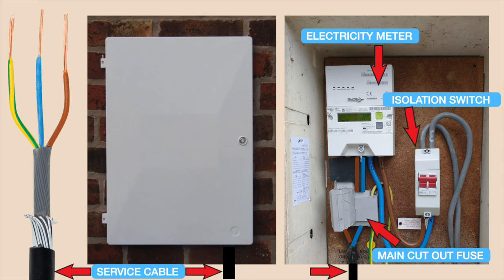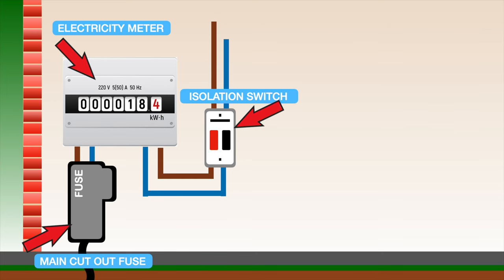On the left-hand side of the screen that's generally what a service cable will look like, and then the left picture shows what a meter box looks like from the outside and the right picture shows what a meter box looks like when it's opened up. The electricity comes in through the service cable at the bottom. It then goes through the main cutout fuse, which is usually either 60 or 100 amps, and this is in place to ensure only a set amount of current can go into the property. It then goes through the electricity meter which calculates the amount of energy being used, and then through the main isolation switch before making its way to the consumer unit.